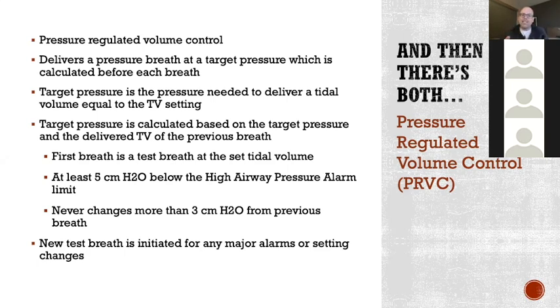But we don't necessarily want volume ventilation sometimes if we're trying to protect those sensitive alveoli, right? Because we're trying for lung protective ventilation strategies, so to have less pressure on those alveoli. So PRVC will do this for us. So what it does is you tell it the volume that you're going for. So I could say I want 12 breaths a minute, 500 cc's a breath. I want that 6 liters through the patient in a minute. And what it would do is it would deliver a volume breath. So it's going to deliver a 500 cc volume breath.